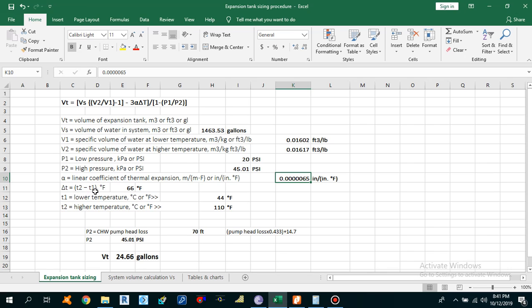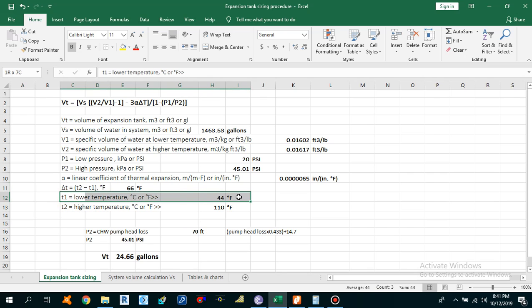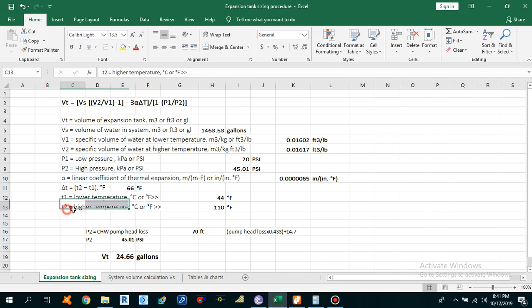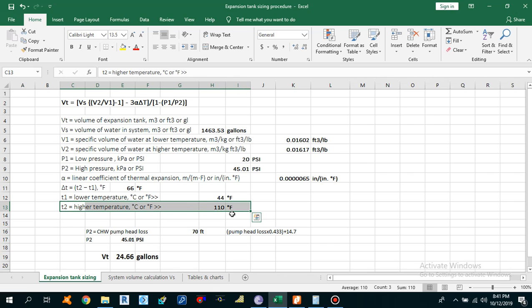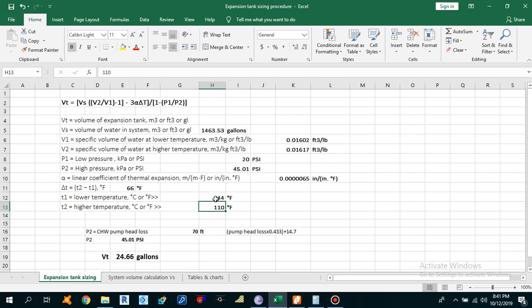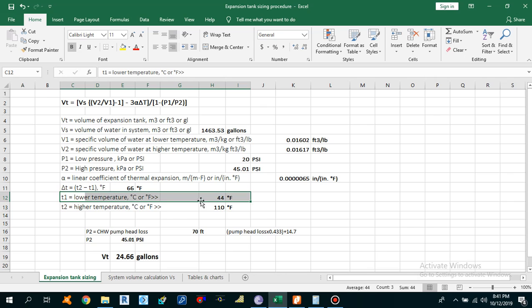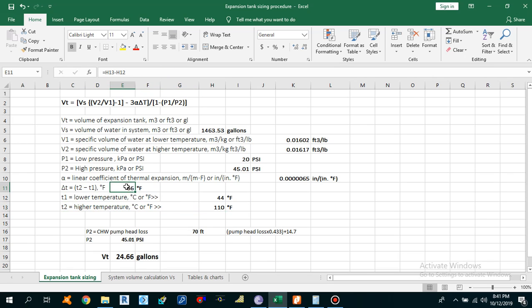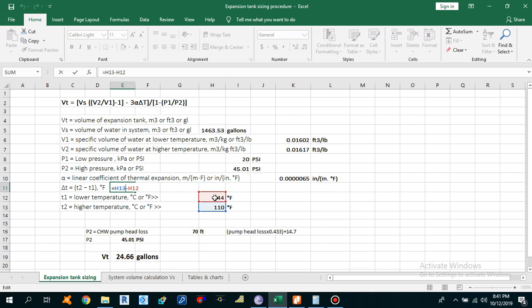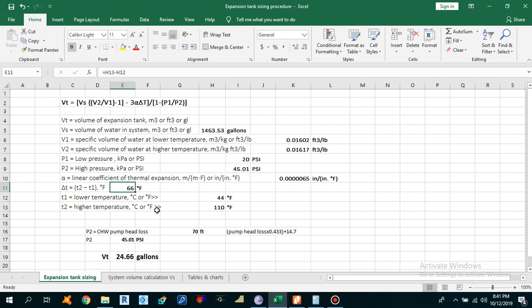Delta T is equal to the higher temperature minus the lower temperature, and this comes out to 66 degrees Fahrenheit. T1 is the lower temperature — our chilled water supply temperature — which is 44°F. T2 is the higher temperature, which is the ambient temperature at our location: 110°F. So delta T = T2 − T1 = 110 − 44 = 66°F.